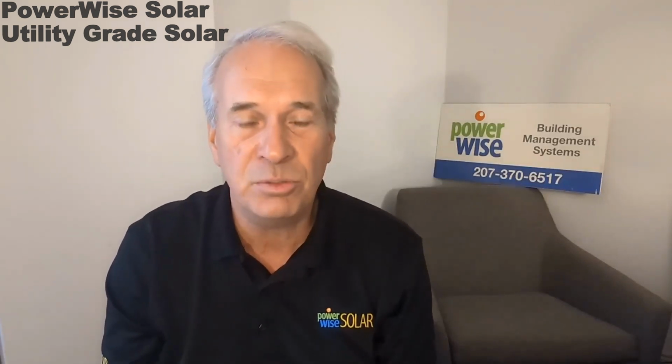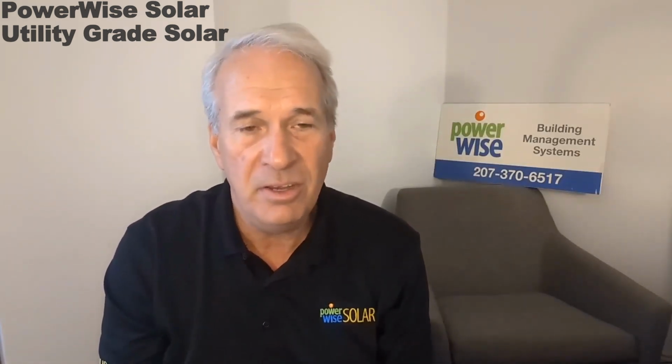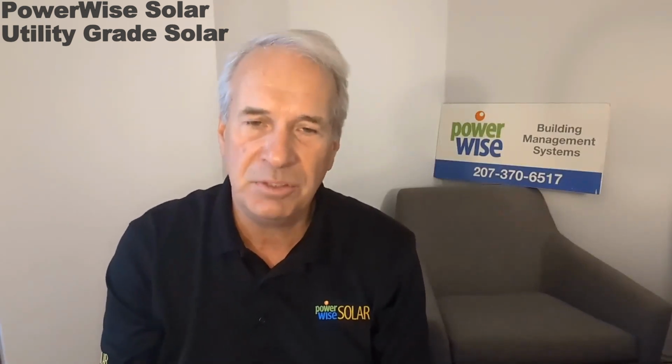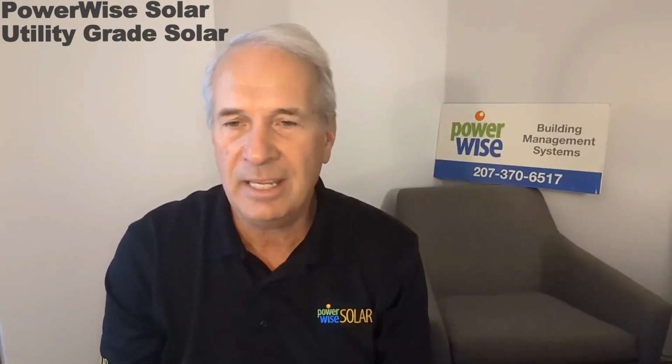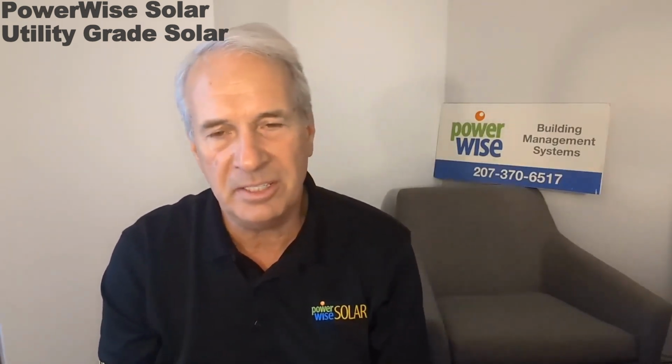Yeah, you're right. This is definitely our key focus, that particular market. And in the US, the utility PV sector is actually the second biggest growth market worldwide. So we have a lot of variation to offer in this segment, and really not a single met station configuration for a utility site is identical. We normally get detailed specifications which we have to meet, or sometimes the client says that it has to be a configuration which meets the IEC 61724-1 standard, with ventilated and heated Class A radiant sensors.